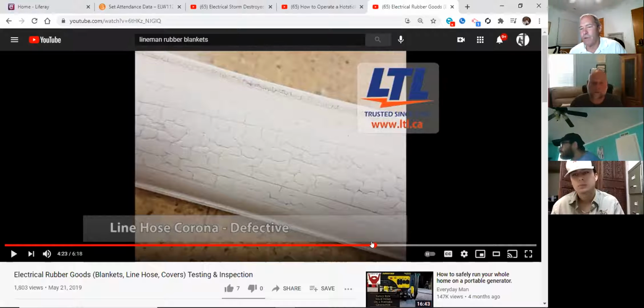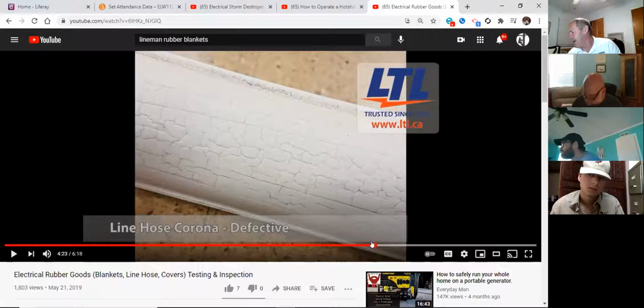Guess what color this hose was when it was installed? Orange, yeah. When he was talking about certain types of damage that can happen, that's ozone damage. Ozone damage comes from having the hose on the conductor for an extended period of time. It's both solar and atmospheric damage that happens to a rubber hose out there in the world. If you see one in this type of situation, you've got to get rid of it also.